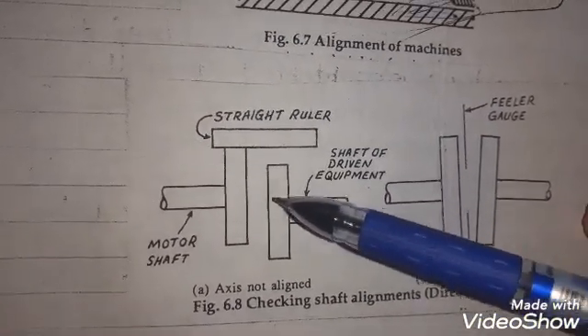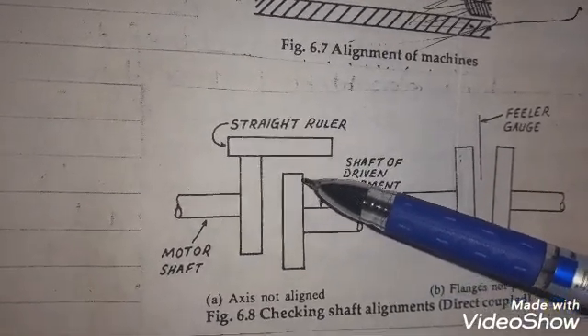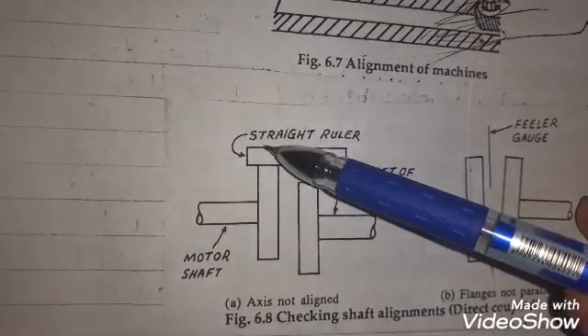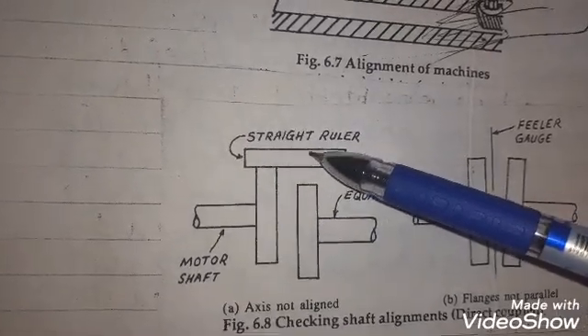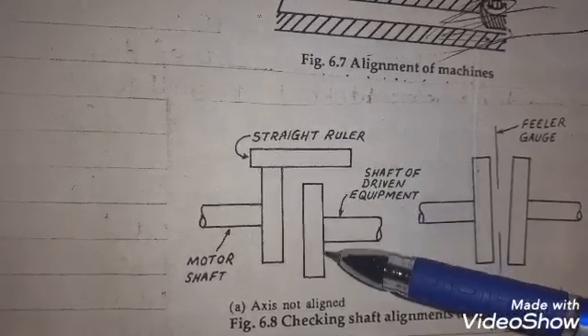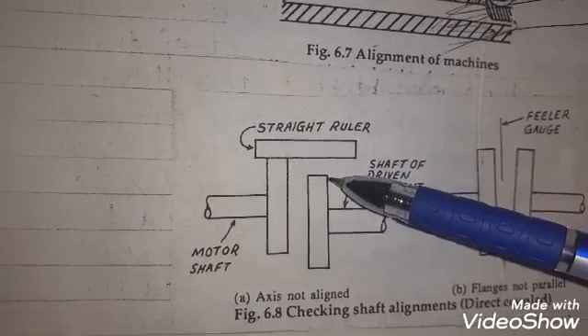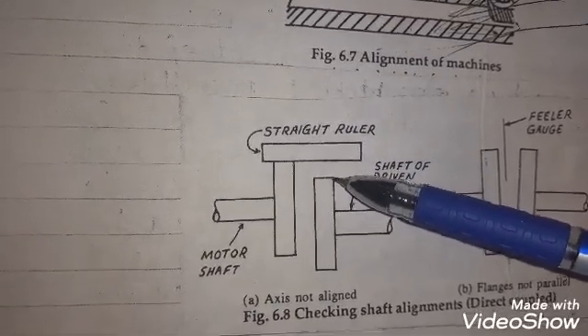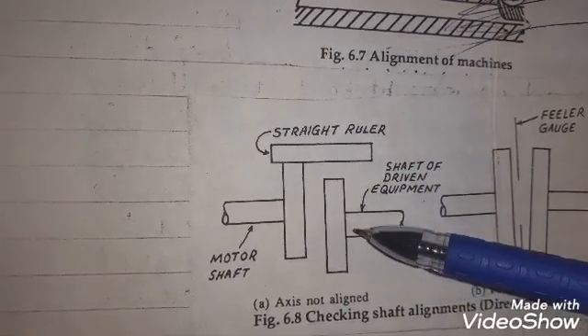The first diagram represents how the axis of the two flanges alignment is checked. For that purpose, put the steel ruler on one of the flanges, that is on the motor shaft side, and check the other driven machine shaft alignment, that is the coupling flange alignment, by rotating it. If it is having a gap as shown in the figure, indicating that the axes are not aligned, then we have to make the arrangement to make them properly aligned.